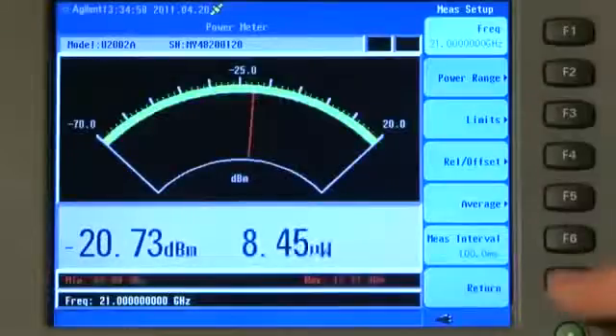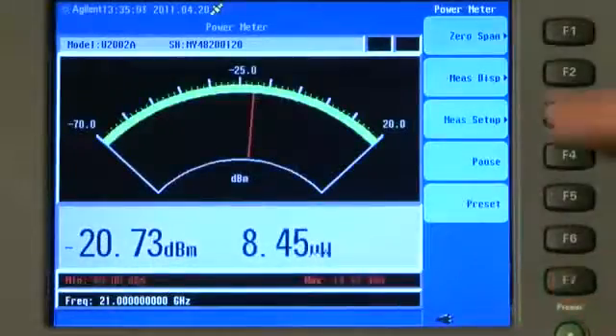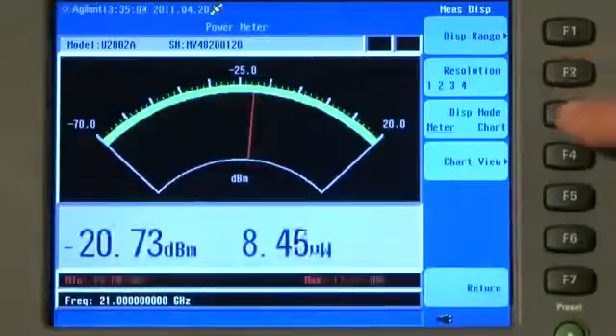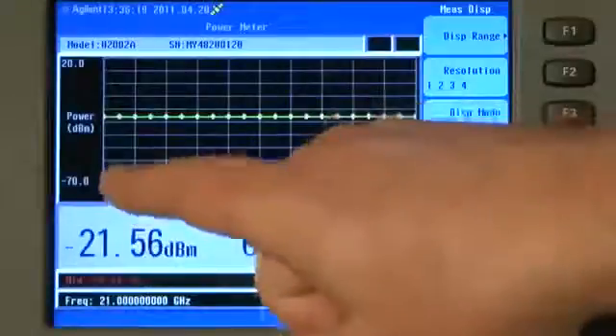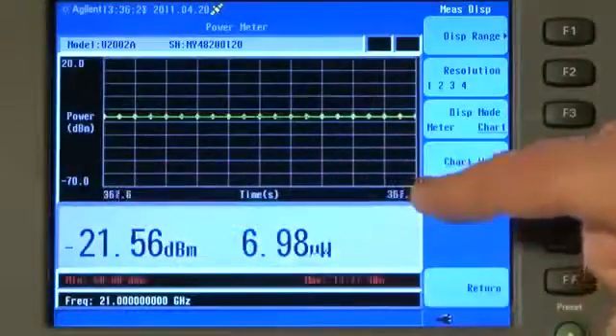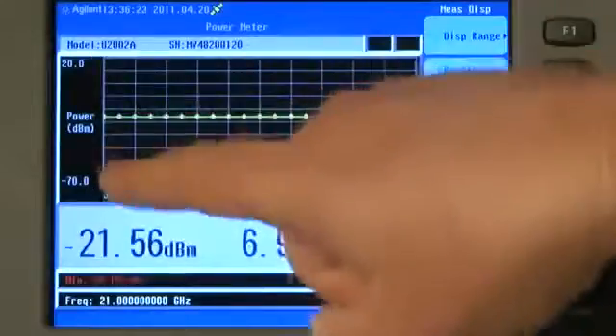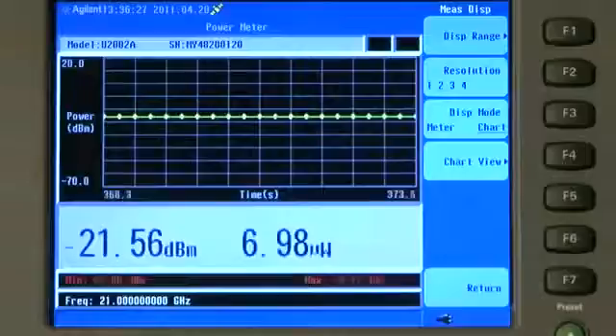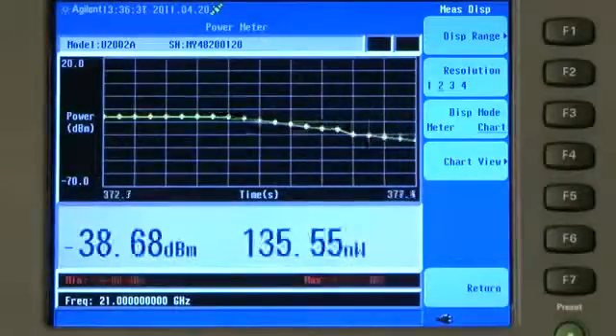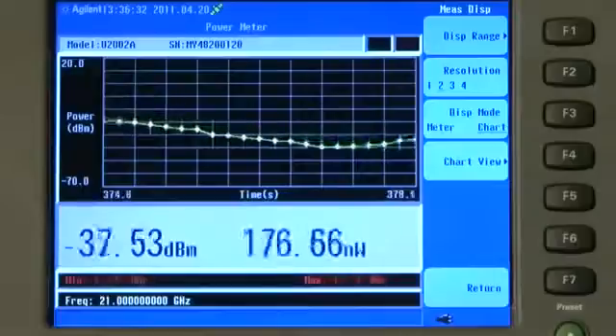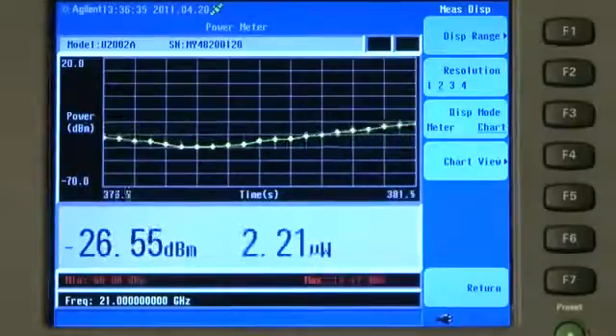But what's even better, if I press Return and press Meas Display, you'll see here that we can change the display mode to a chart recorder. On the chart recorder display, we have time on the x-axis and power in dBm on the y-axis. So if we're trying to track, again, a microwave fading situation, as the level drops down, you can see that we are recording that on the chart recorder display.